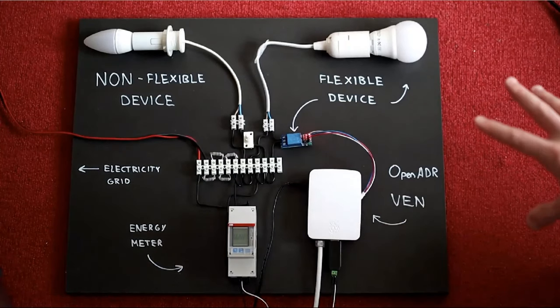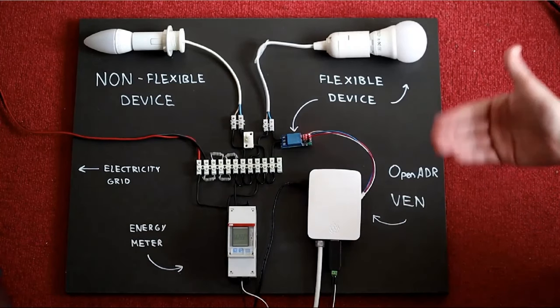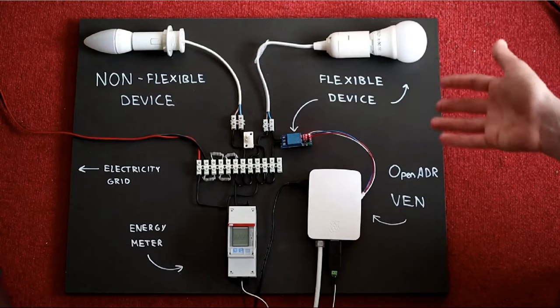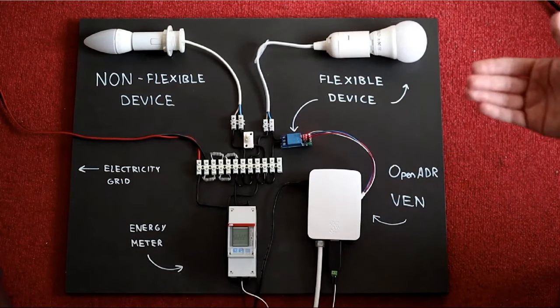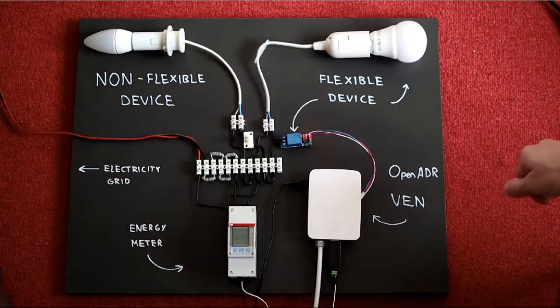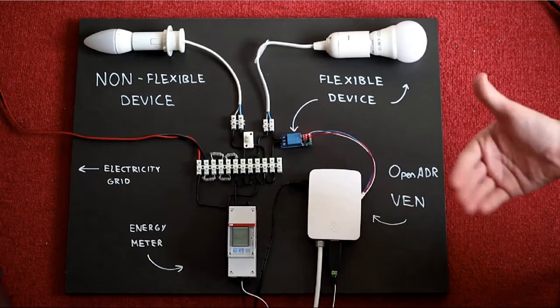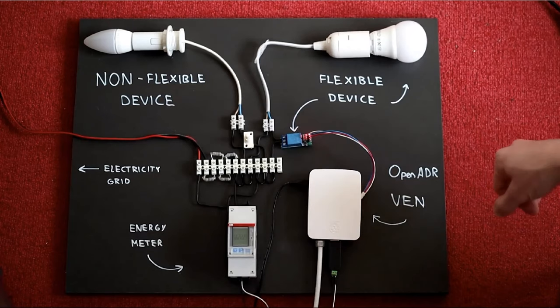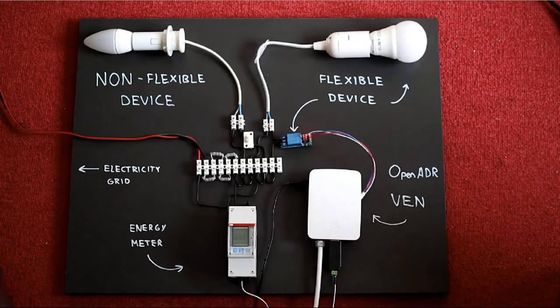Everything is powered by the electricity grid. I've designed it so that turning on these devices will lower the voltage on this part of the grid, and that's something we report to the VTN. The VTN is set up to receive these reports and looks at the voltage being reported. Whenever it exceeds 230 volts, the flexible device can turn on. Whenever it dips below 215 volts, the flexible device has to turn off.